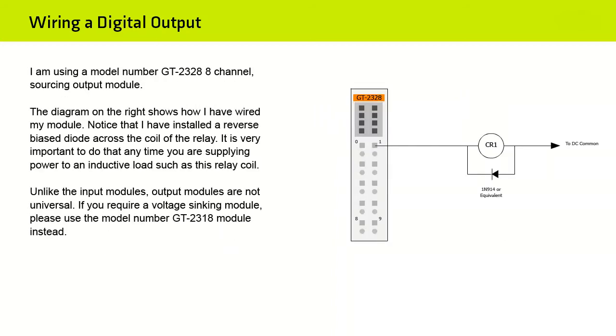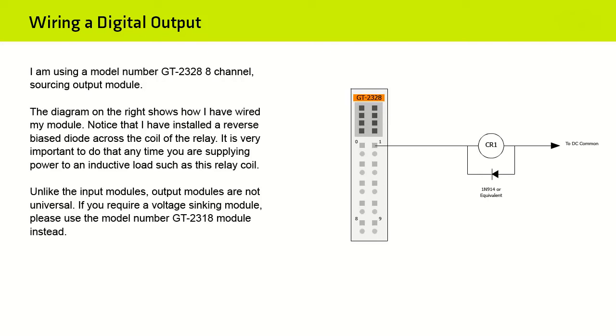I am using a model number GT-2328 8-channel sourcing output module. The diagram on the right shows how I have wired my module. Notice that I've installed a reverse bias diode across the coil of the relay. It is very important to do that any time you are supplying power to an inductive load, such as this relay coil. Unlike the input modules, output modules are not universal. If you require a voltage sinking module, please use the model number GT-2318 module instead.